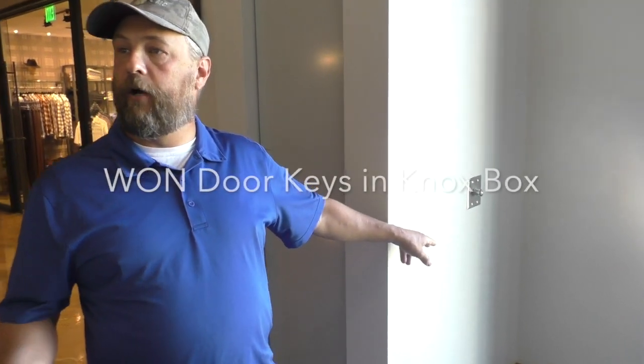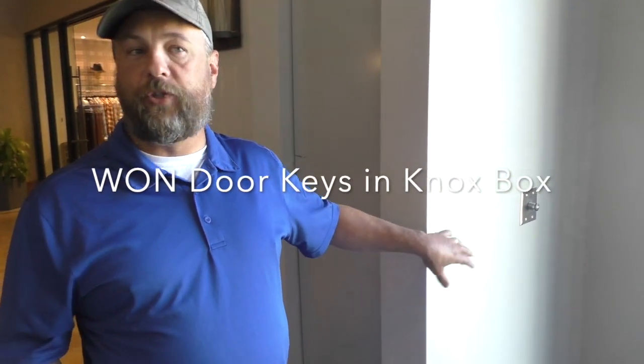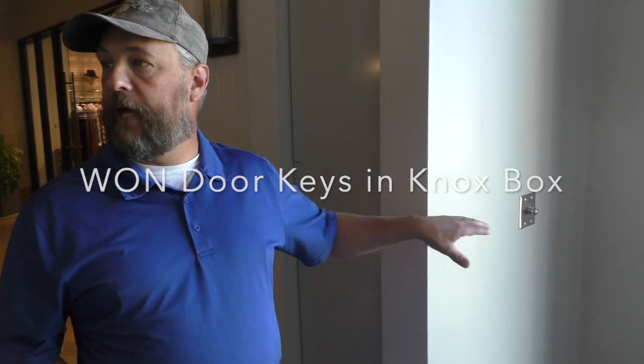Once the door is shut, you only have one way of operation during the alarm, and that's through the key switch. So you can now manually override open and closing here. This door, if you were to pull out that key once you have it open, but we're still in alarm, after a few seconds it's going to revert back to the alarm state. So it's going to close again. So be sure, before you pull the key out, that we actually have the alarm reset. By resetting it, go back to the fire command, reset your panel, make sure all the red lights are off, and then you can go ahead and remove your key.